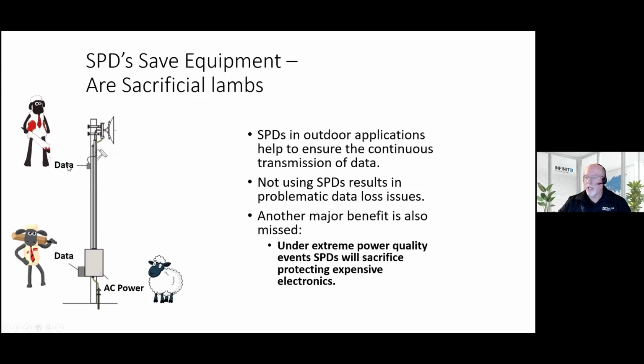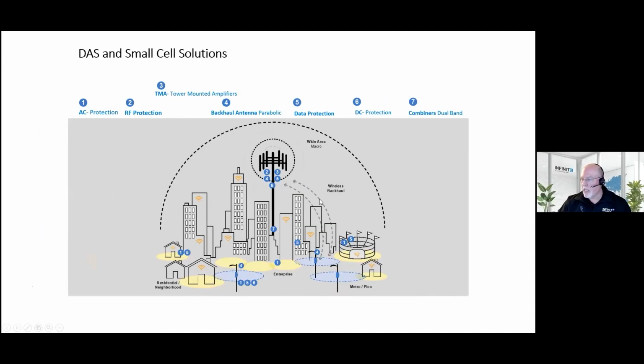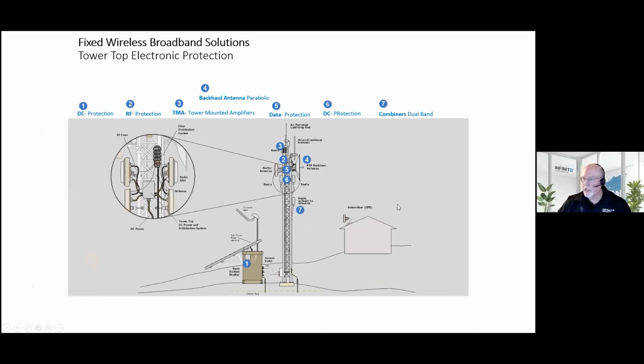And so you'll put a data surge protector at both ends of that same data cable. They may be marked at each RJ45 connector, line and load, the line being the source of the surge. So in this scenario, with the two data protectors, the line connections of those data protectors will be looking at each other because the cable itself between them is the source of the surge. And this is just to show you that you'll need surge protectors for various things all over the place, in different applications.